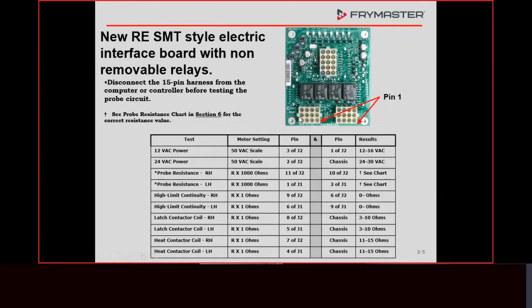The next thing we're going to discuss here is contactors. Very simple. It's a relay. You've got a coil which is 24 volts AC. When we put voltage to that coil, it becomes a magnet and pulls those contacts down. We've got pieces of metal that touch each other that complete our circuit. All right. The latch contactor never switches any current if the fryer is operating properly.